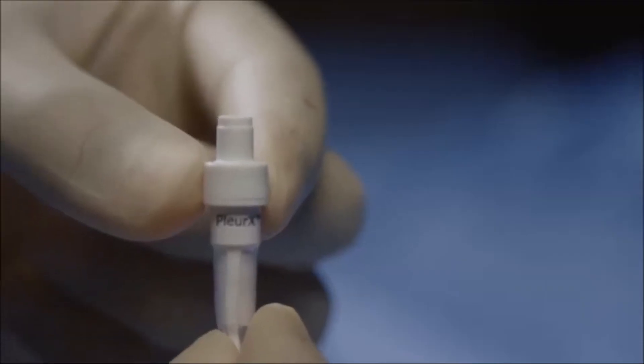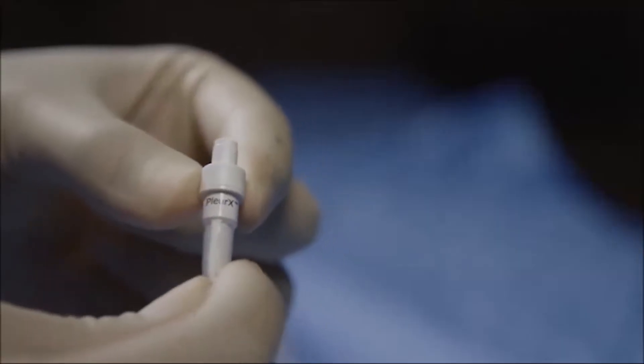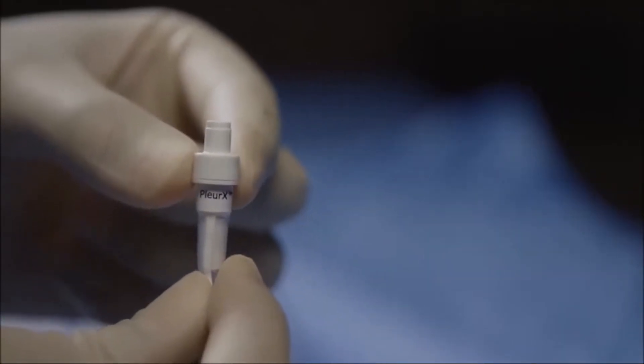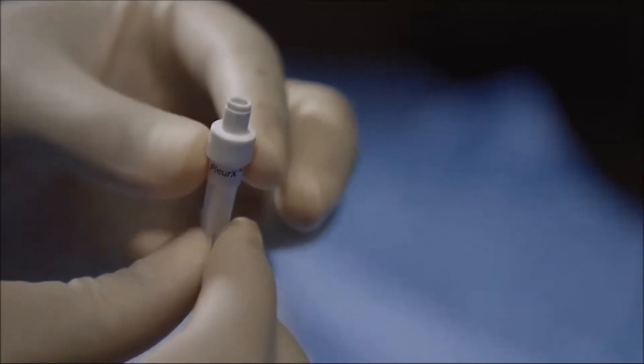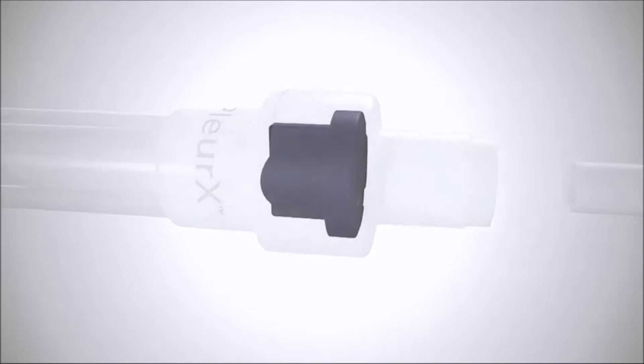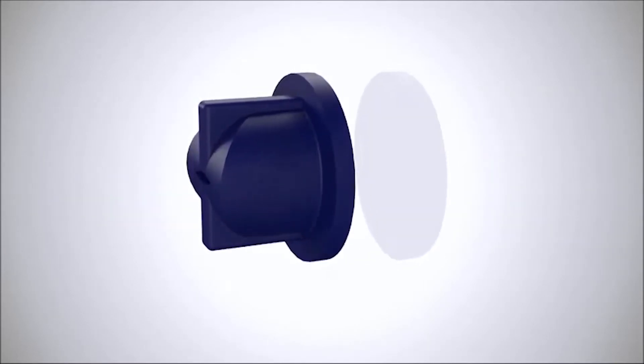The catheter valve is designed to prevent the passage of air or fluid in either direction unless it is accessed with a PleurX drainage line, access kit, or PleurX vacuum bottles. The primary valve keeps the catheter closed when the patient is not draining. The secondary valve provides a backup seal around the access tip when the patient is draining.